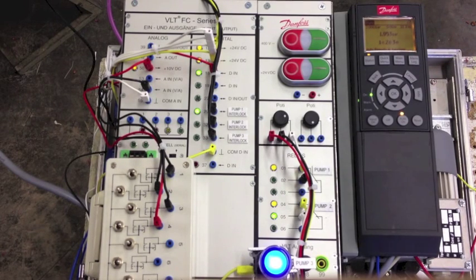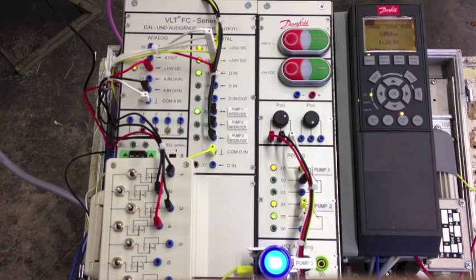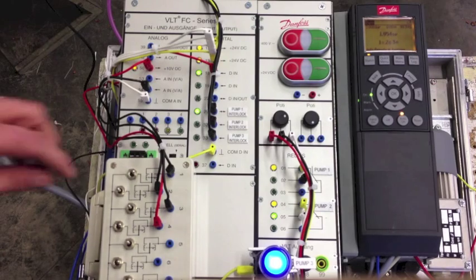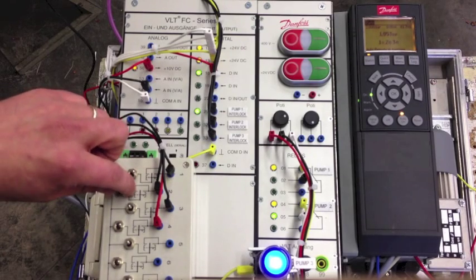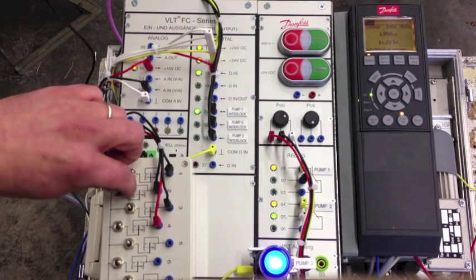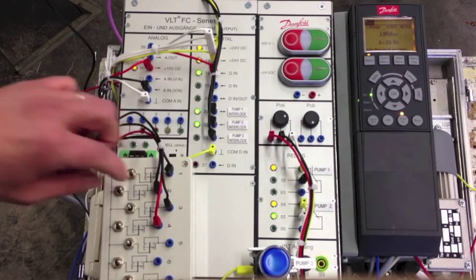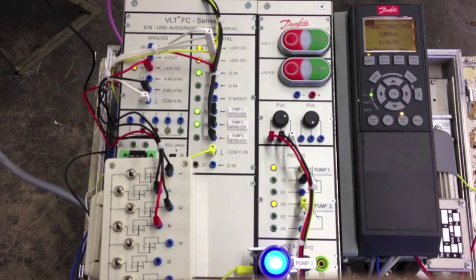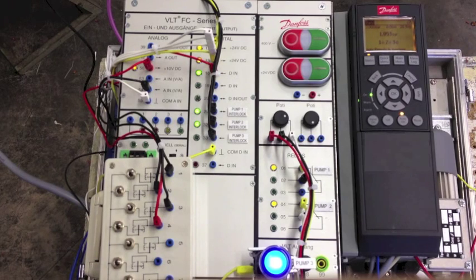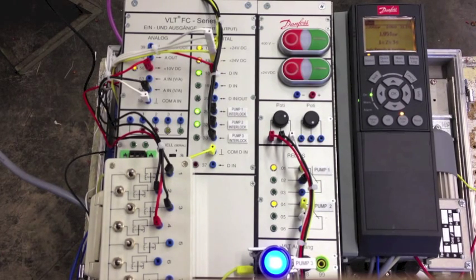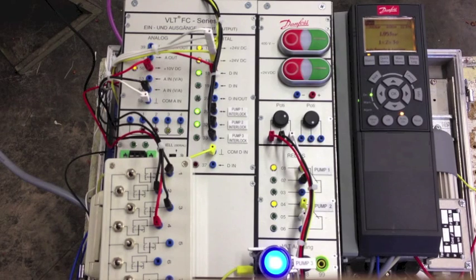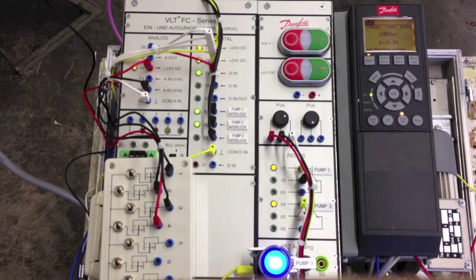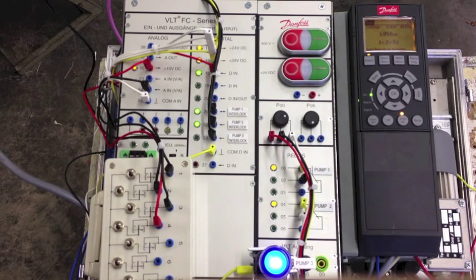At this point be careful because if we interlock the actual main pump, so the second pump, the drive performs a very smart operation. First of all it stops the third pump, then goes to 0 Hz. It activates the second relay and activates the third relay and starts the pump.